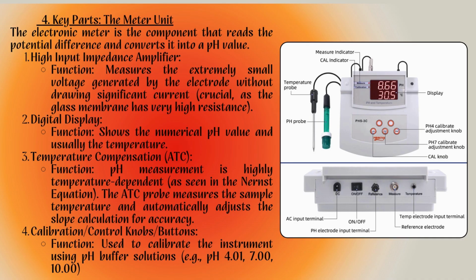Third and very important is automatic temperature compensation, or ATC. Since the Nernst equation shows pH is temperature dependent, the ATC probe measures the sample temperature and automatically adjusts the meter's calculation. This ensures the pH reading is accurate regardless of the sample temperature. And finally, the calibration control, used to adjust the meter using a known buffer solution to ensure accuracy.